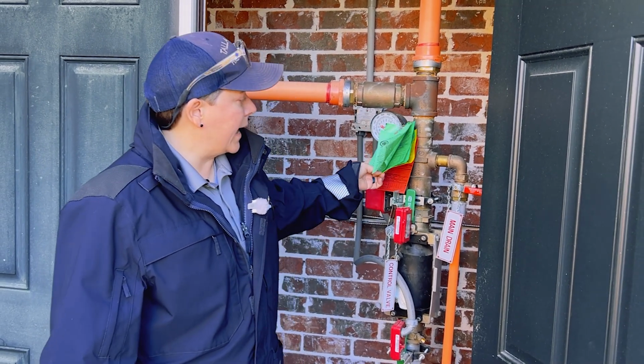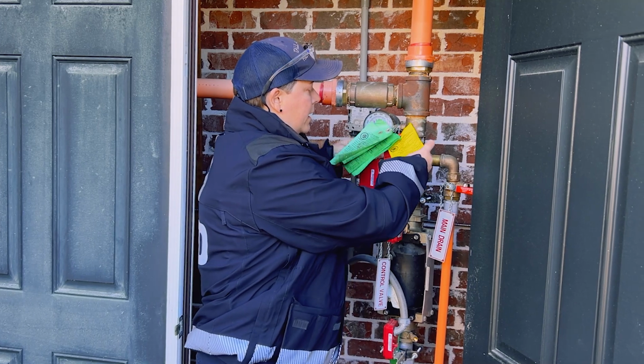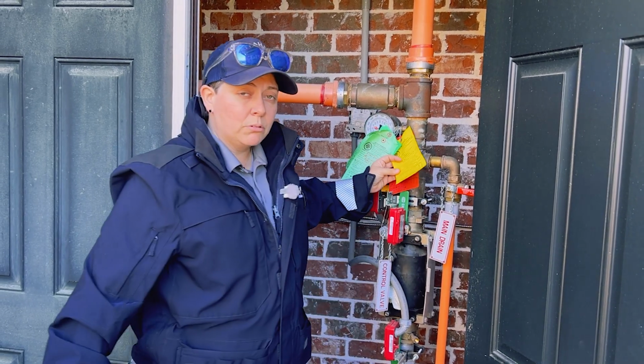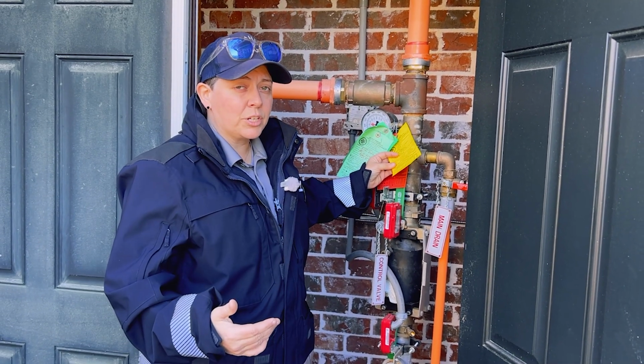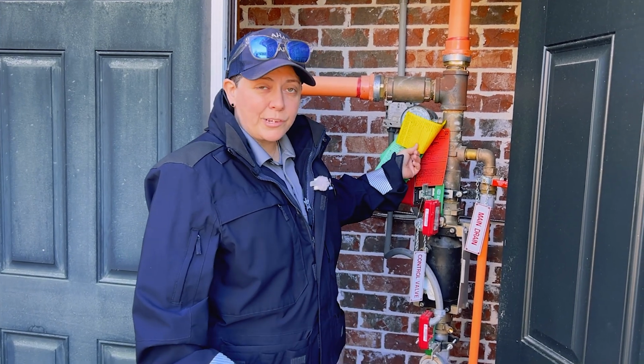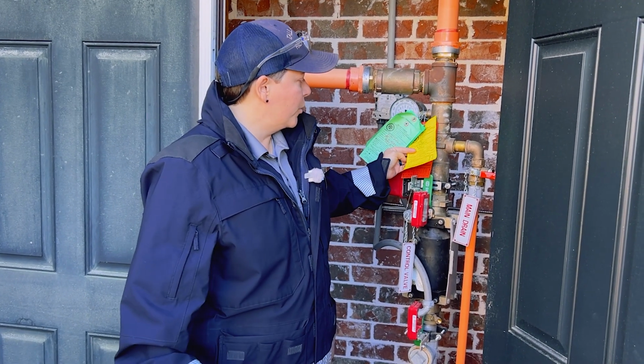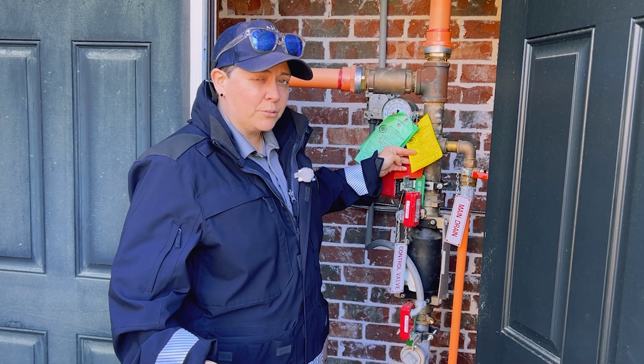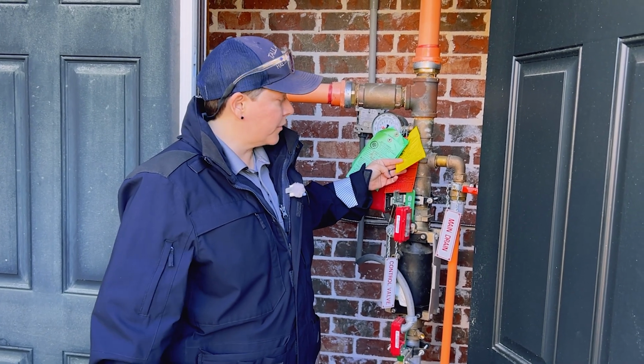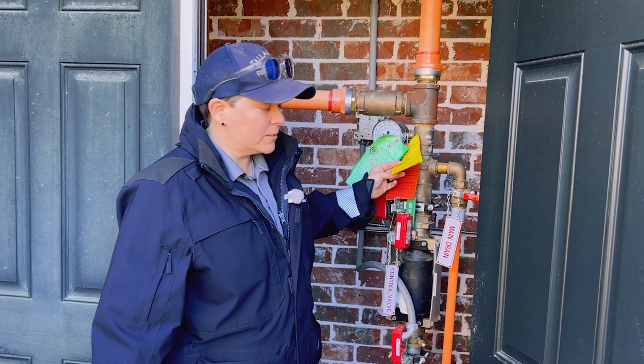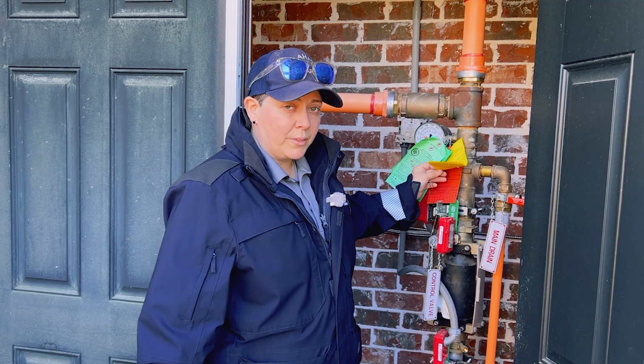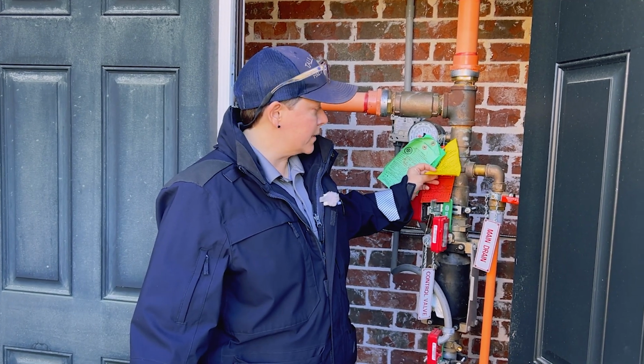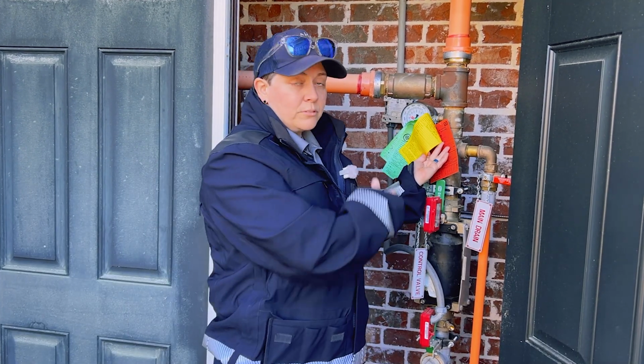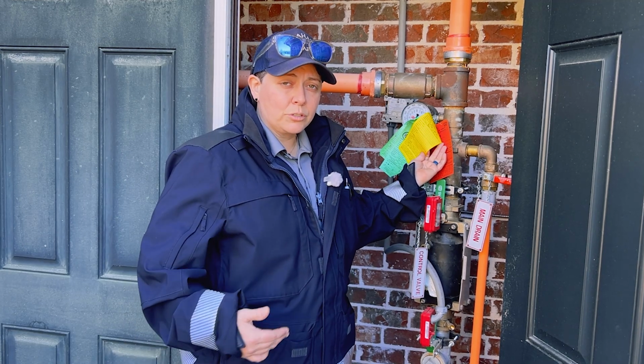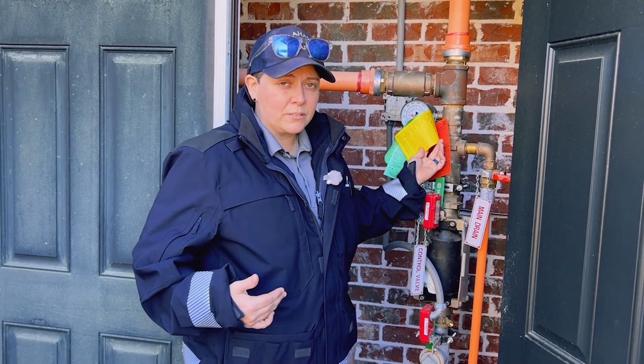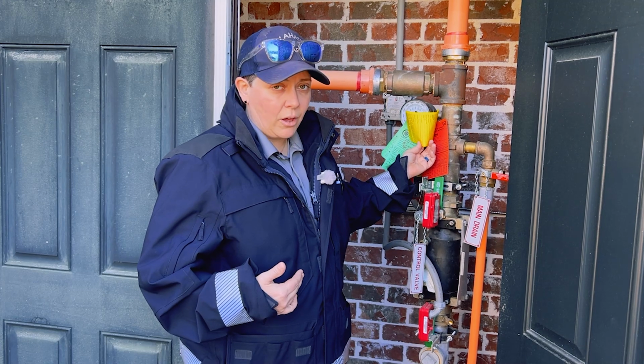If you have a yellow tag, that means there might be a small issue, and it could be something that is expired, such as a valve or even a pressure gauge. Those actually expire. Whenever the company comes out and does the annual test, they'll put one of those tags on there. If there is a minor deficiency, they should come out within 180 days and fix that deficiency. And then once they fix it, they're going to put notes and comments on the back. The fire inspector should go ahead and get that report to see what that deficiency was and make sure that it was fixed in the allotted time.